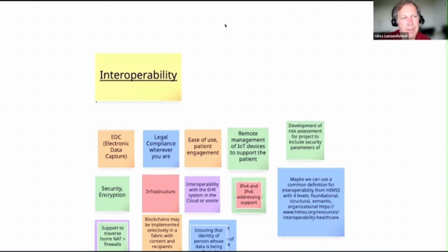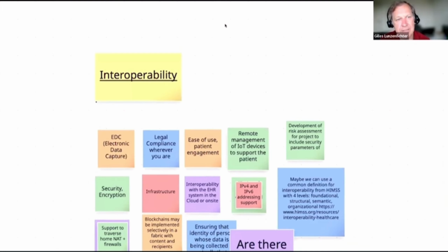If I tie back to the question of are we sure it's the person using the device? We had use cases in heart insufficiency where it's critical to monitor the spike in weight increase, right? Because this is the first sign of a decompensation by the patient. But of course, the weight scale, usually you put it in a bathroom. So in a bathroom, you might have, again, the cat, you might put a luggage on it. You might have the grandchild who jumps on it because it's funny to jump on a weight scale. And then on the telemonitoring side, suddenly there are some stupid data points that come in. So we had such a situation in a real deployment of telemonitoring of heart insufficient patients.